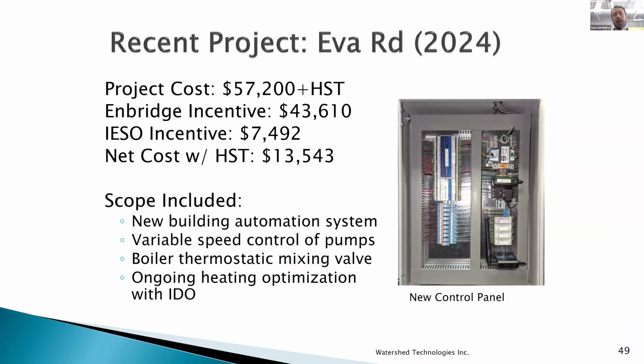So in this project, we installed the building automation system and variable speed drives for the pumps. Because the boilers are non-condensing and we want to operate them at lower temperatures, as Wesley was saying, and non-condensing boilers are not designed to operate below 135 degrees Fahrenheit, we had to retrofit a mixing valve onto the boiler to allow that to happen. And then we optimize the heating output of that system over time.